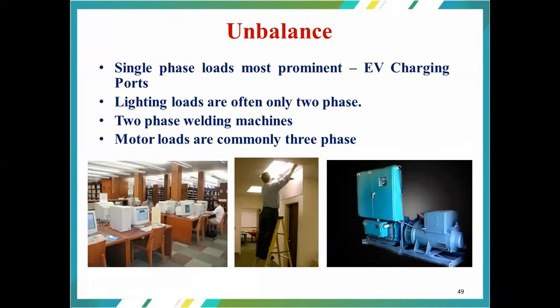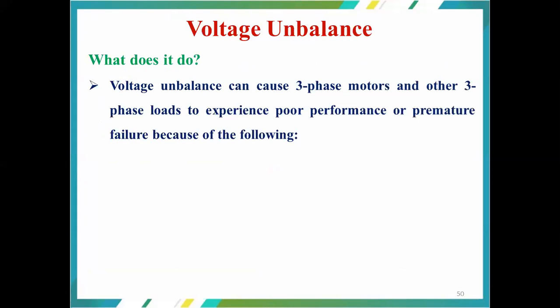And the next one is the unbalance from single phase loads, most prominently the EV charging ports at the particular transformers or facility. Lighting loads are often only 2 phases, again street lighting or the general lighting facility at a particular location. 2-phase welding machines are often connected to the local transformers or the local load. Motor loads are commonly 3-phase, so they won't be an issue. Somehow they balance the unbalances existing in the 3-phase system.